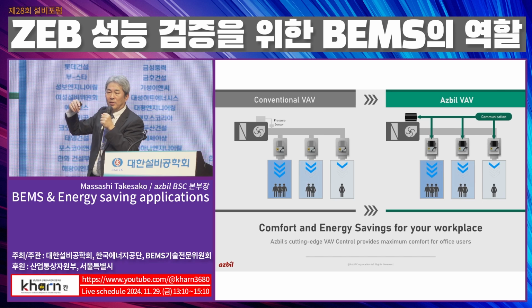Same as the water side. On the water side, our control target is to maximize the valve opening as much as possible, to minimize the friction loss from the control valve. The air side concept is also the same: maximize the damper opening of each VAV, then minimize the friction loss from the VAV. That is the basic concept of our control.